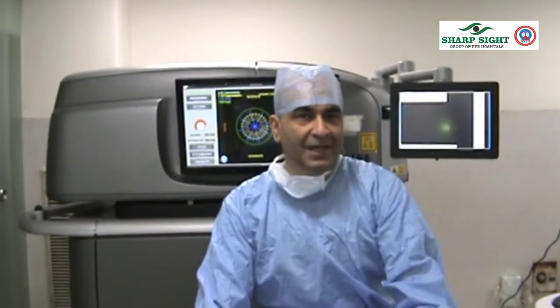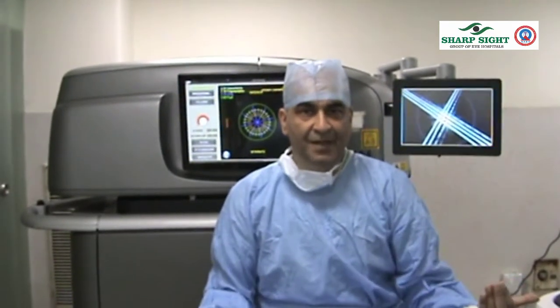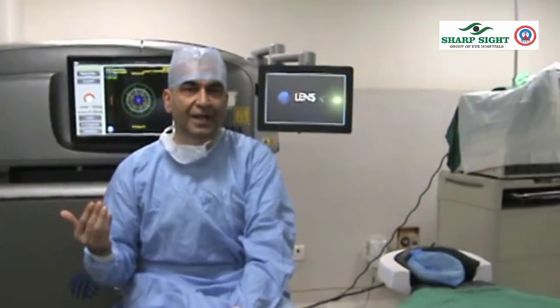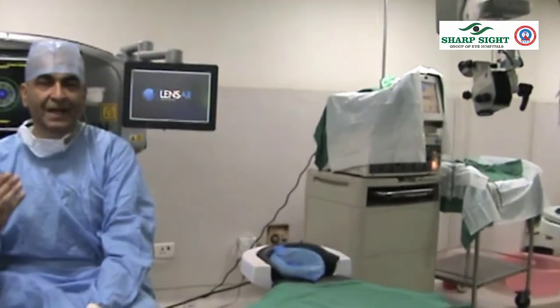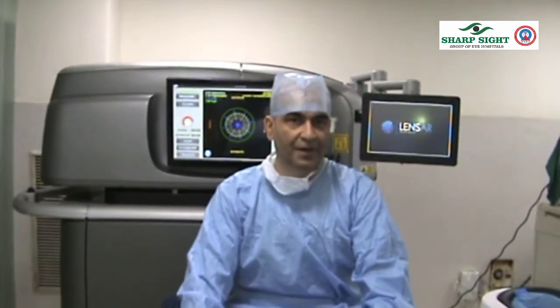One last point where LENSAR outscores all other machines is that this is my main operation theatre where I do my regular cataracts. I do not need to move the machine away from the main OT — it remains within the same OT. The LENSAR is a mobile unit; I can shift it from one OT to another. So even if I have three OTs running, I can keep shifting the machine between them, which is a huge leap when I have a large number of FEMTO cases to be done.